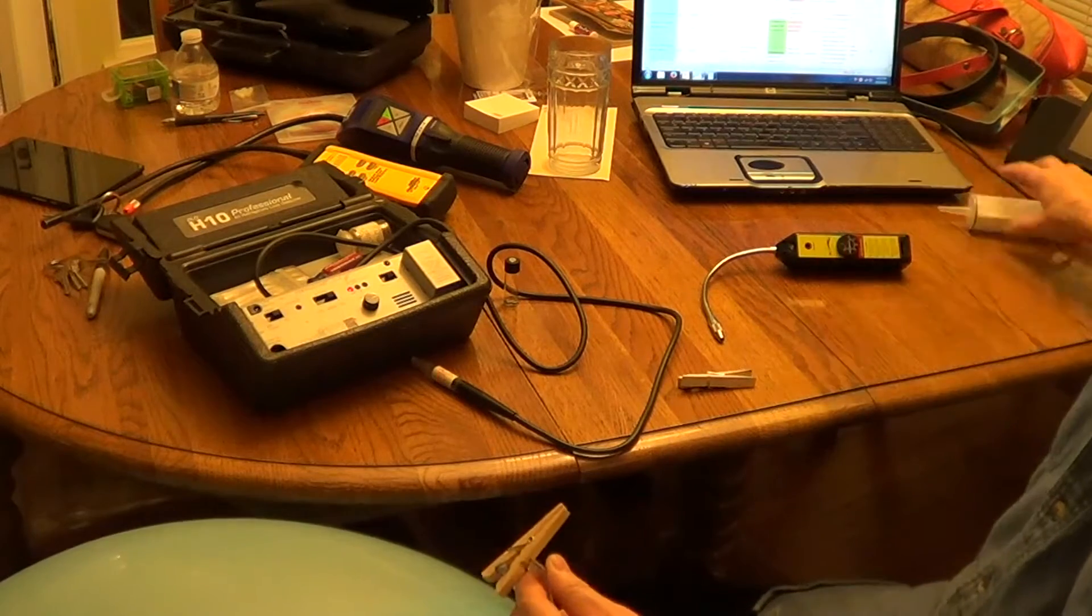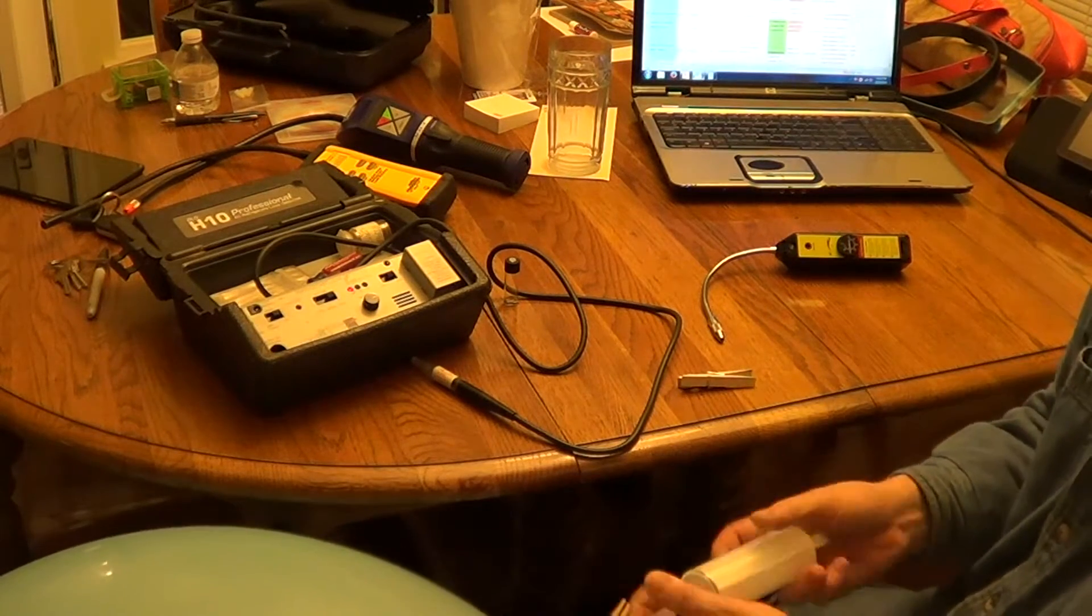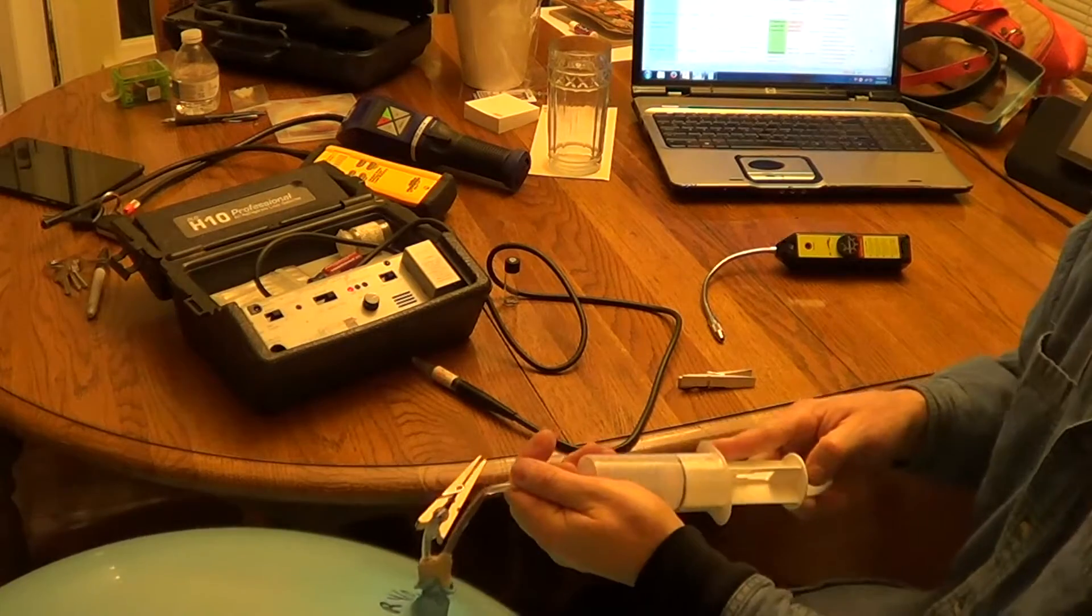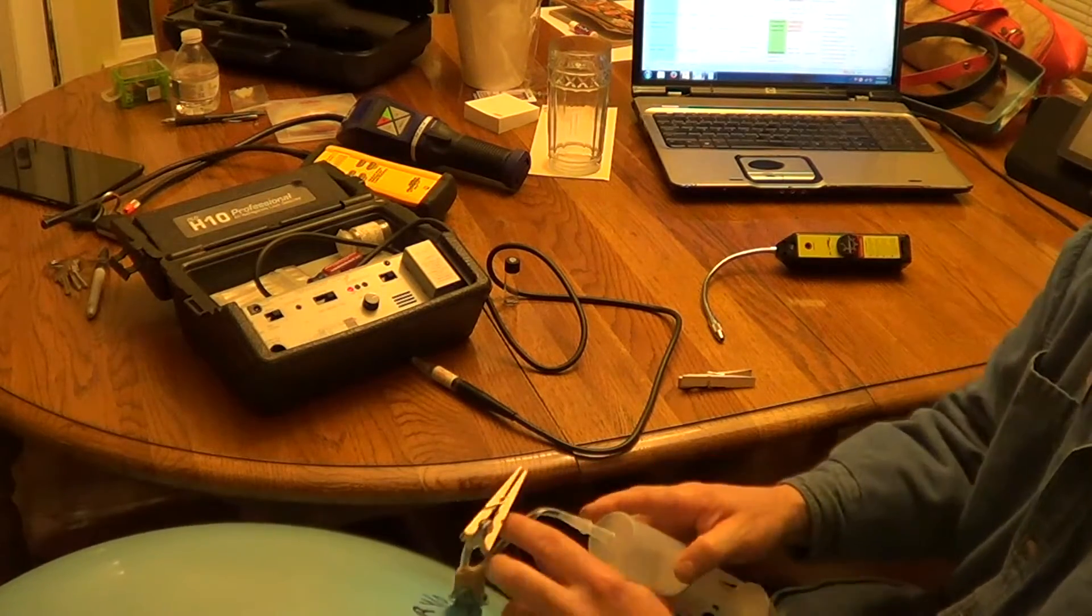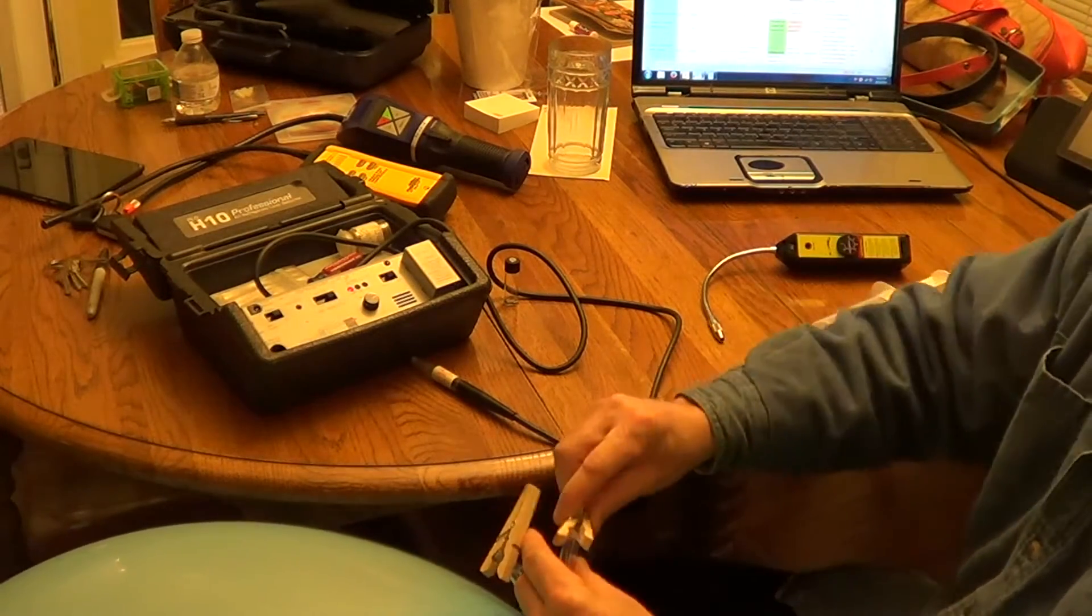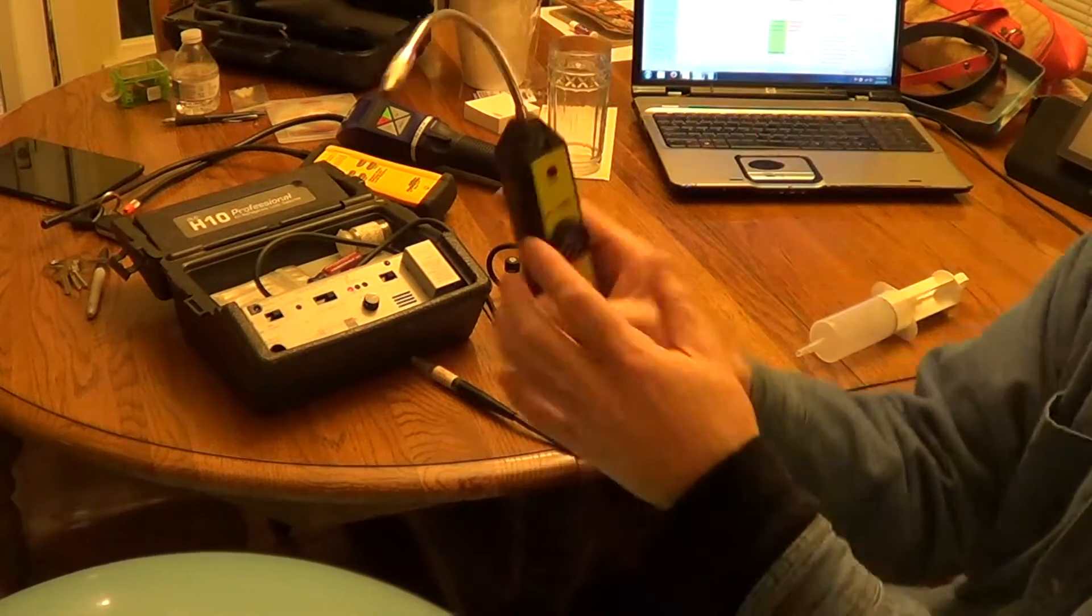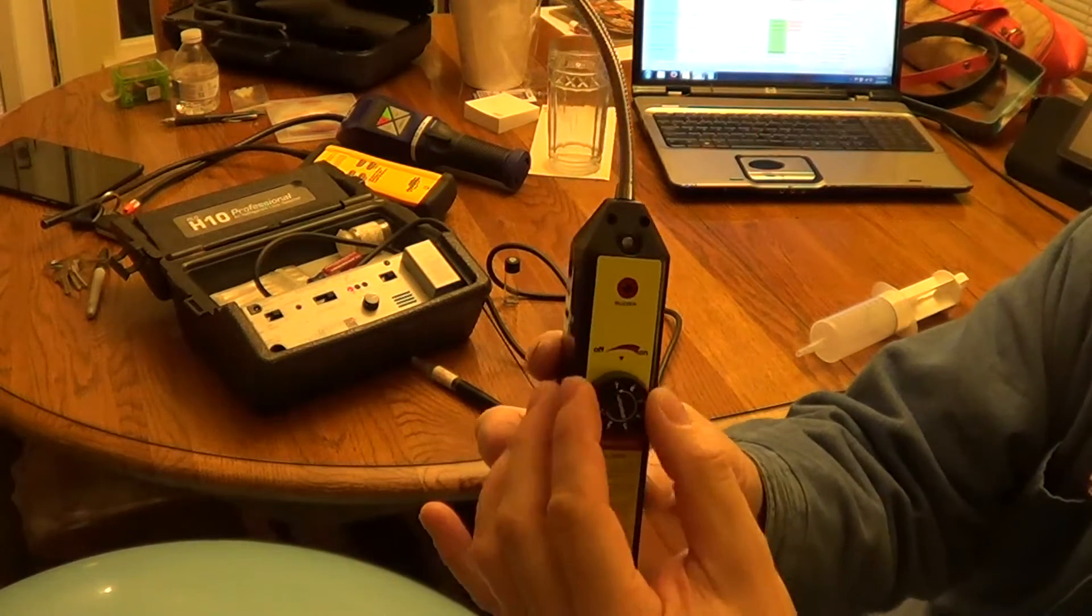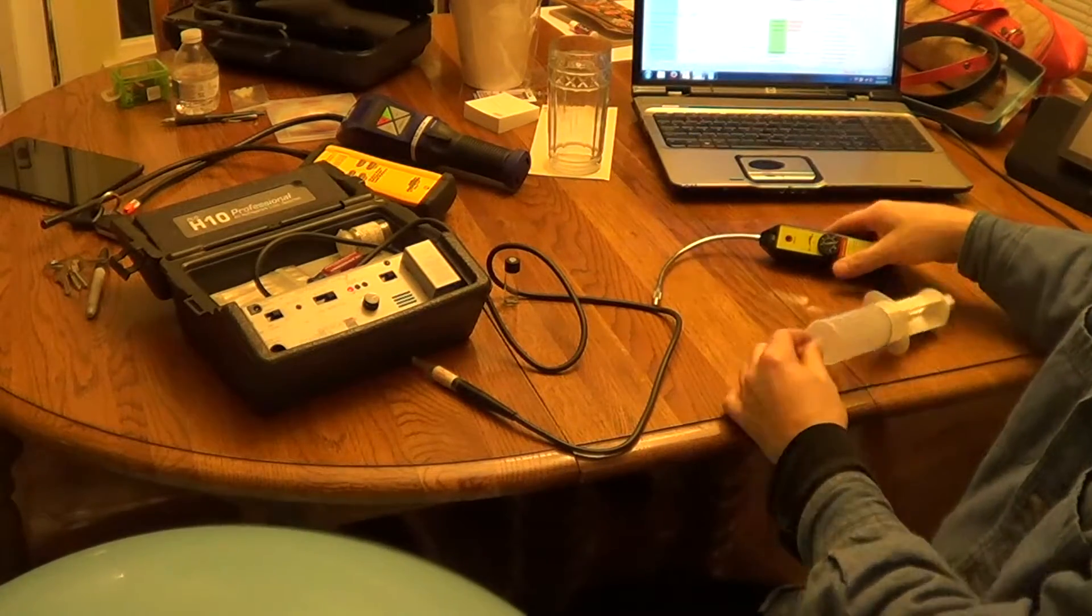This balloon is 10 parts per million. Just filling my syringe here, 10 parts per million R410A. Here's a little $20 Chinese leak detector. I'm going to show you the difference in the sensitivity.